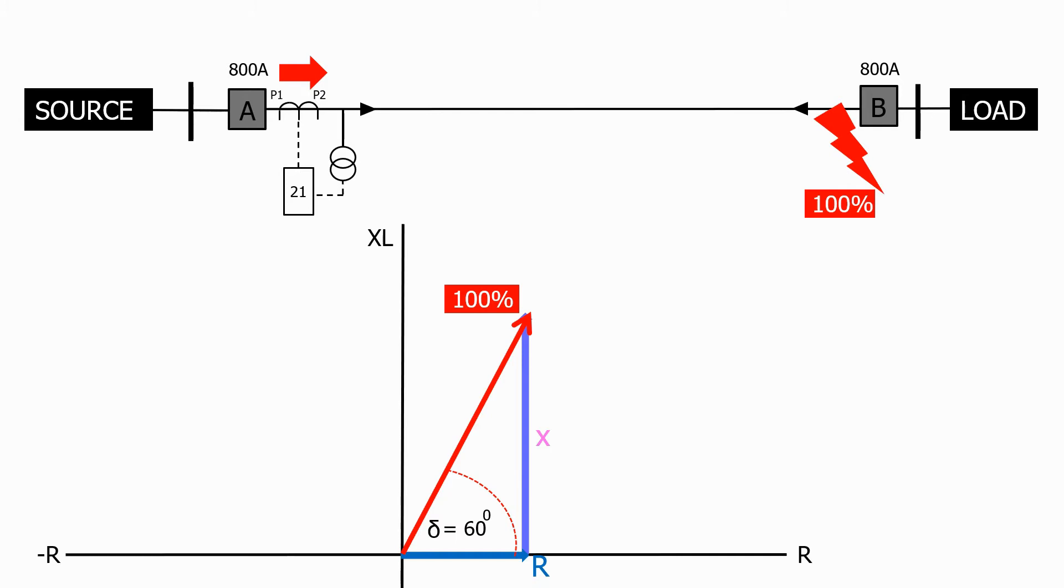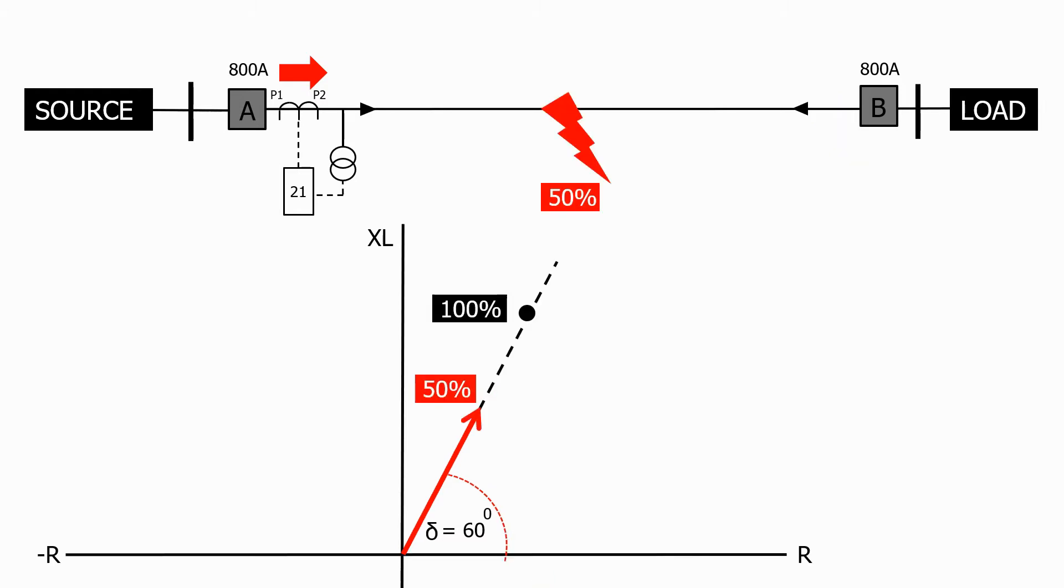Let's now apply a fault at 50% of the total line length. As we're halfway down the line, the resistance and reactance values will be about half of the full line impedance, but the characteristic angle will remain at 60 degrees.